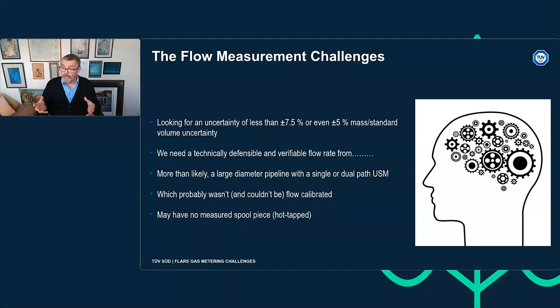It probably wasn't flow calibrated because it can't be flow calibrated. You know, where do you take a 36-inch flare line with complex inlet pipe geometry? Where do you take that if you want to calibrate it between 0.05 and 100 meters per second? The facilities don't exist. It may have no measured spool piece, unlike a highly engineered custody transfer ultrasonic meter. It may just have transducers welded into the pipeline. Nothing inherently wrong with that, but you don't have the same control or confidence in your geometry.